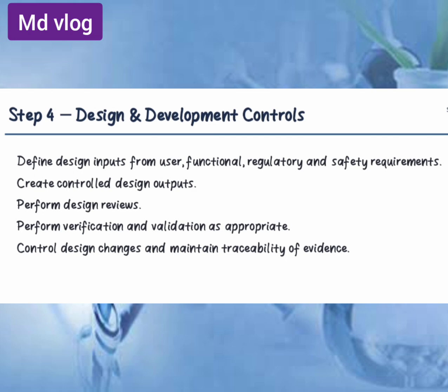Step 4, design and development controls. In this, verification and validation play the most important role. Verification asks, did we build the design correctly against requirements? And validation asks, does the finished device meet the intended use and user needs?